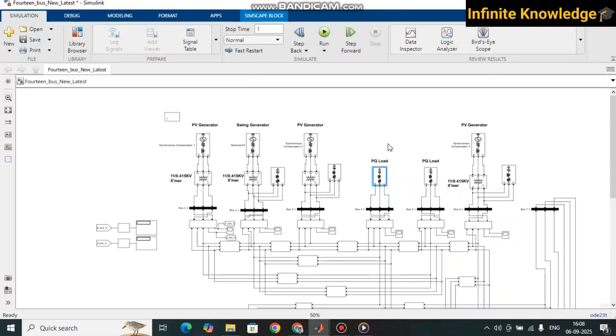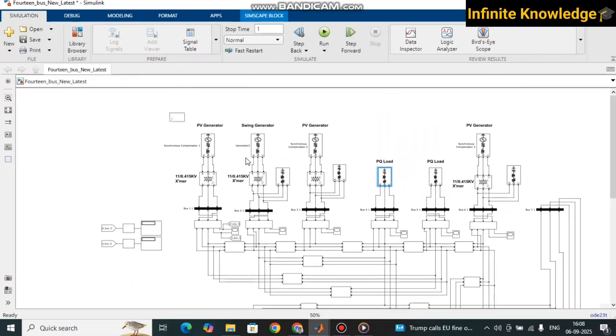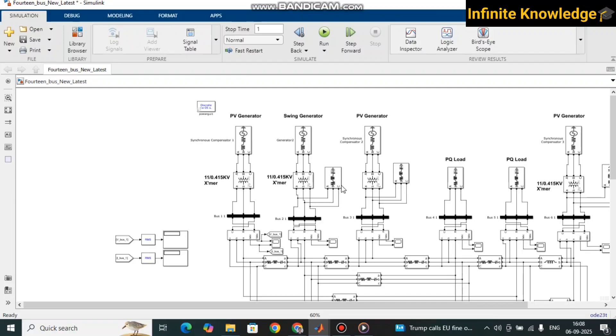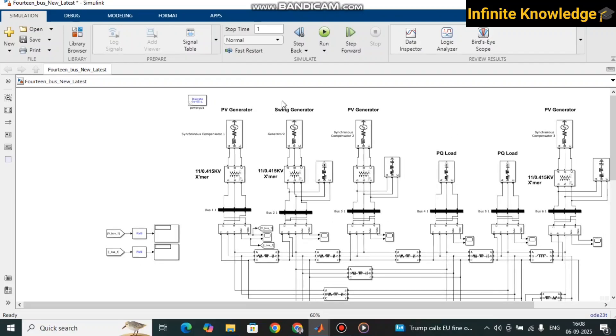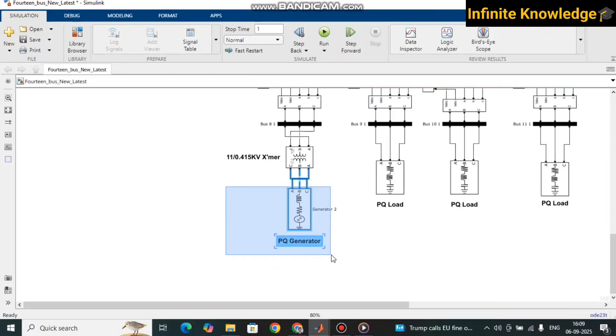All the loads are connected and one generating bus in every system is a swing bus. The swing bus is the reference bus — it is the main generator, the biggest generator in the system. All the small generators and compensators follow the frequency and voltage level of the swing generator. Another generator type is the PQ generator.